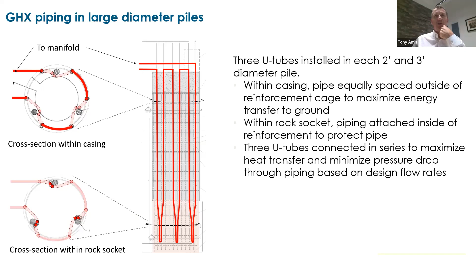The key is obviously how we feed each of those piles back to the submanifold. In this case, we've got a west zone and an east zone, so the site is split into 2. What you can see here is 3 loops connected in series and then run back to submanifolds. Each of these submanifolds had about 7 or 8 piles connected to them.